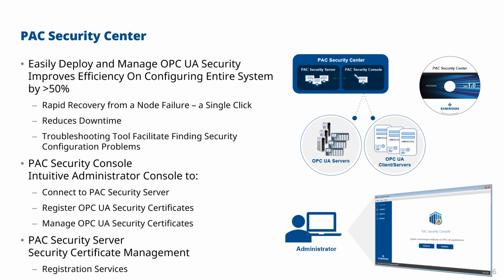The PAC Security Console provides an intuitive administrator console allowing you to connect to the PAC Security server. The server is the process that actually stores the certificates. It allows you to register OPC UA security certificates so that they can be used by multiple devices, and it allows you to manage those certificates, including creating them, checking their validity, and withdrawing them as well. The PAC Security Server also supports security certificate management with registration services to make sure that all of your high security devices can talk to each other.